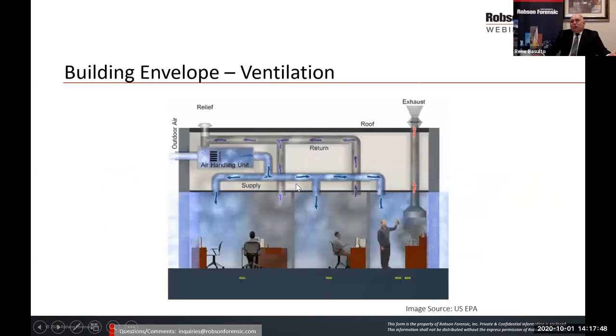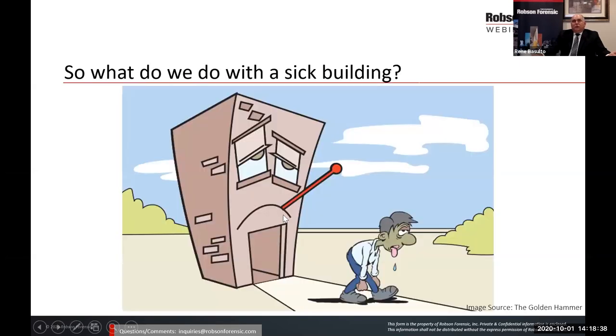So when you don't have that ventilation, this graph will show you that you'll get the contaminants, especially in the area where the occupants are. Because the occupants alone are releasing the contaminants, or you have sources of contaminants, whether it be cooking or some type of production or some type of hoods for hazardous conditions, you will get that accumulation as well if you don't have adequate ventilation. Just so you have an idea of this graph, I can explain a little bit. This would be outdoor air coming in. This would be your equipment that's moving the air, the air handling equipment, with either heating or cooling coils or both, distributing the air. And this would be the air coming back and being relieved. If you have too much of that air, not enough of the outside air, is when you end up with inadequately ventilated buildings.